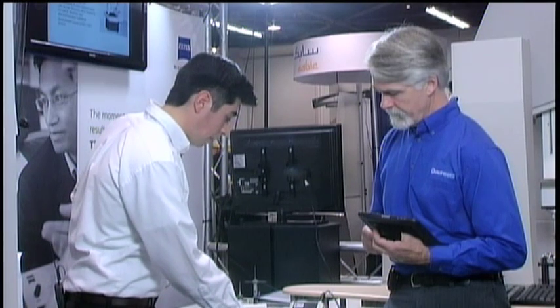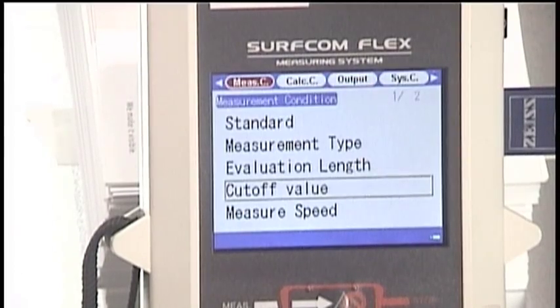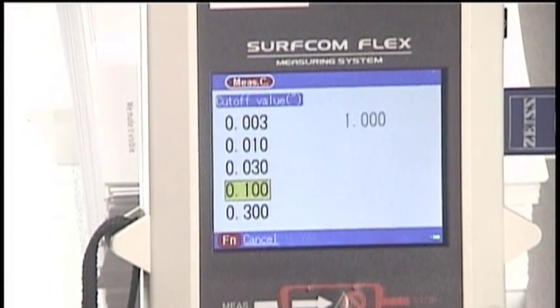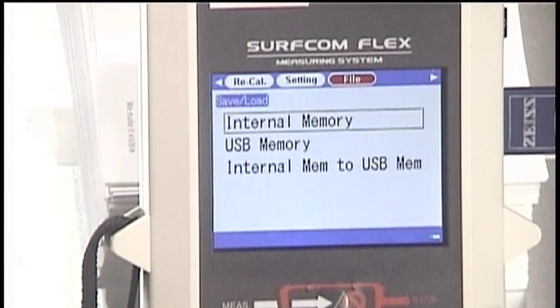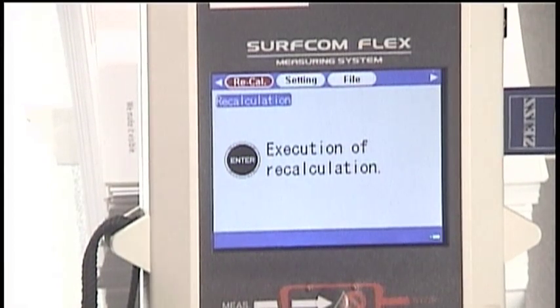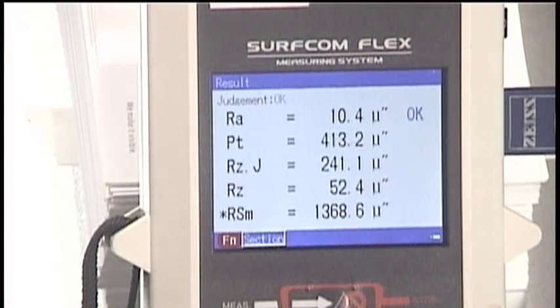Yeah, another great feature about the Surfcom Flex is that at any time you can recalculate data by resetting different parameter settings. If you input the wrong cutoff frequency, for example, you can go back, change it, and recalculate that data. So actually, I'll go ahead and do that right now. I'll go back into my menu and go into some of my settings here that I want to change. For example, let's say I wanted to change my cutoff value from 0.1 to 0.003 because that was the correct value to use. So it's going to take the data that's currently loaded, which is the one that we just measured right now. And as soon as I hit enter, it's going to execute a recalculation of our measured data. And so as soon as I change it, you see a different value now for the RA.